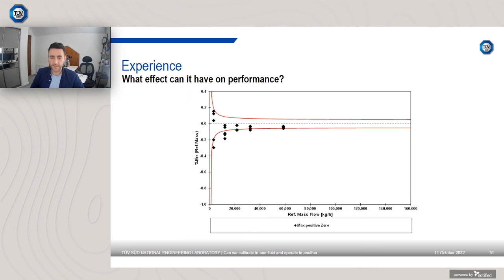Now, if you remember back to that slide where I showed you the zero stabilities, that gave you the maximum permissible zero. Now, I only had it in the positive direction, but you can multiply it in the negative direction. And what that simply means is a Coriolis meter is bidirectional. Ultimately, in our diagram, let's say we're flowing from left to right, and that's forward. You can actually set the device up for reverse flow, and you can flow from right to left, or you can have it bidirectional, where it could flow in either direction.